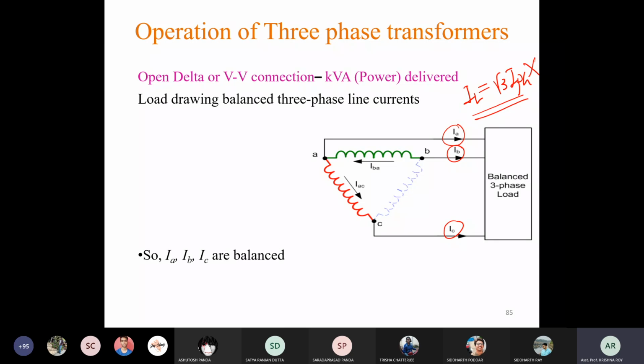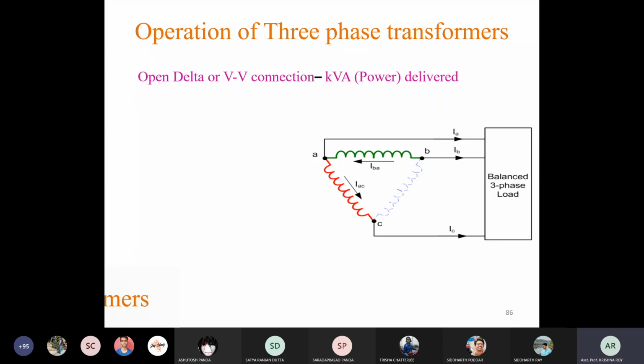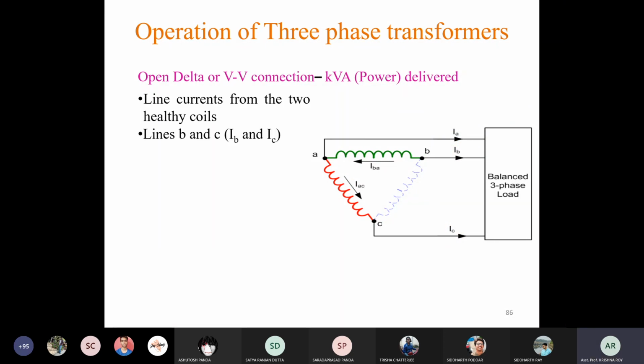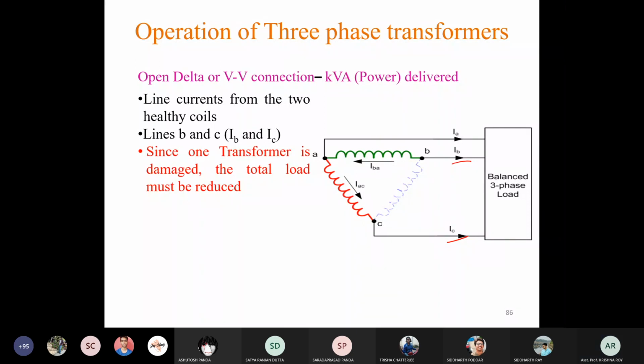So how to handle this kind of situation? Let us see, here 3 line currents are present and they are balanced. Now what will be their magnitudes? Line currents from the 2 healthy coils, that is line B and C, are IB and IC. So these are the two currents from the healthy phases. And since one transformer is damaged, the total load must be reduced. So as per our previous example, we cannot supply 60 kVA, that is for sure. So now the question is, can we supply 40 kVA? That we have to check.